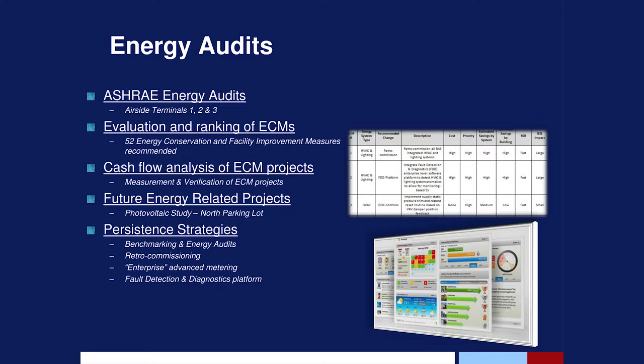We didn't audit airside 4 because it was getting a new central energy plant. It was getting about 40 air handlers replaced. There were a lot of projects concurrent in airside 4. So we did ASHRAE Level 1 energy audits of airside terminals 1, 2, and 3, roughly about 1 million square feet of conditioned and active space. We identified 52 energy conservation measures and facility improvement measures during that process.